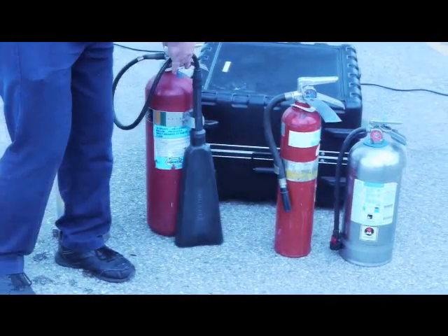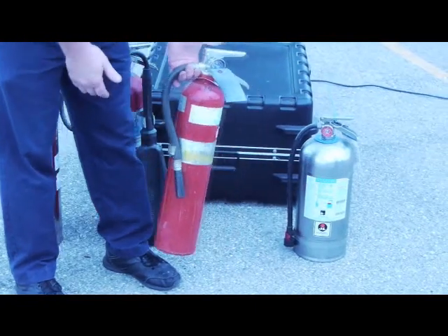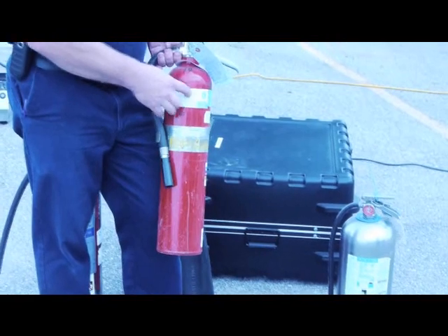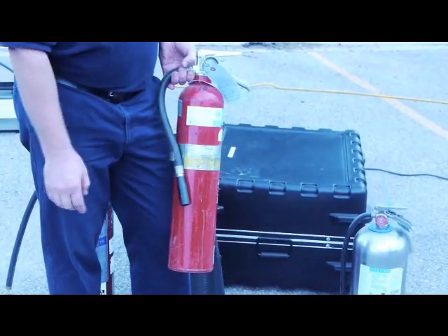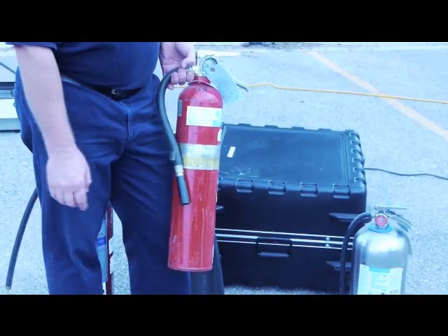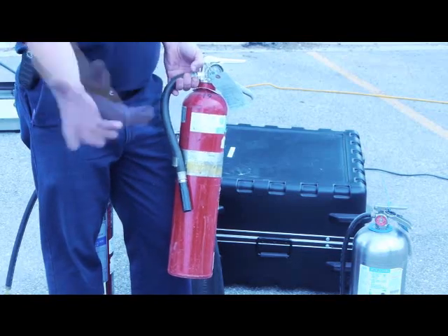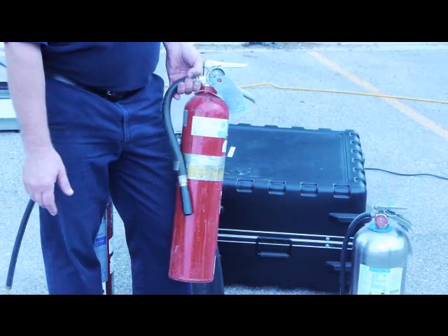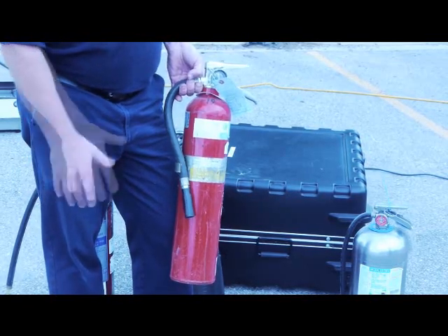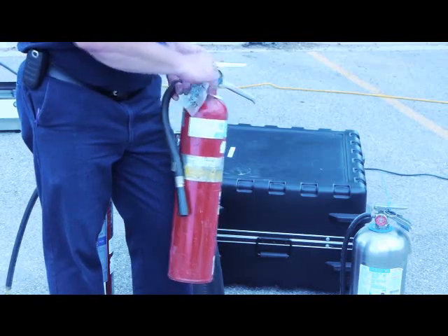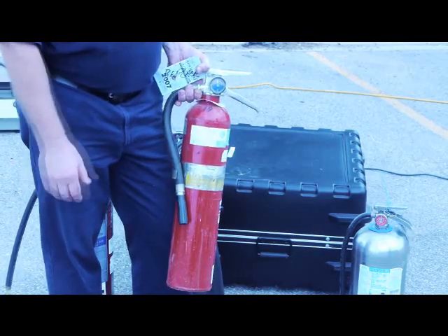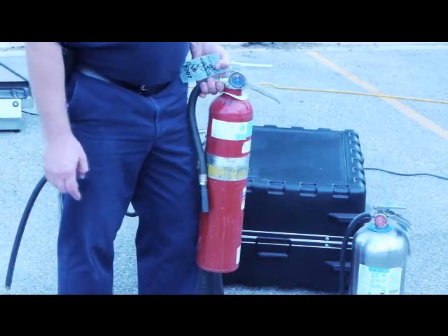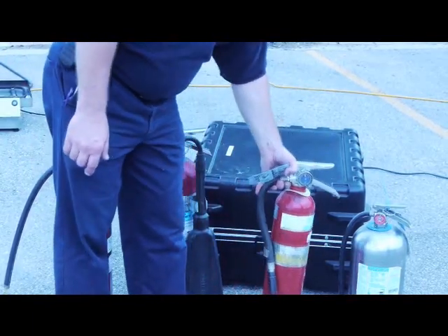Third is going to be the most common extinguisher you will find. Now this is a little older one, and the label's faded, but the pictograph is going to show A, B, and C. This is a dry chemical extinguisher. It contains a fine powder that will eliminate the oxygen in the area and give a little coating to any of the fuels that are burning at the time. So with that, this is what you're going to find in most applications everywhere you are. This is good again for A, B, and C class fires. So this is the workhorse that you'll find in most of all your locations.